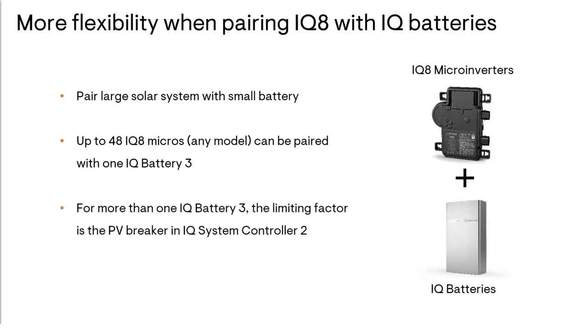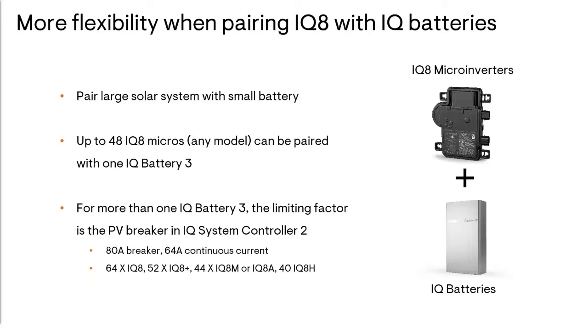Now, if more than one IQ battery 3 is being installed, which is going to be the case most of the time, I imagine, the limiting factor then is the 80 amp breaker in the IQ system controller, which means that up to 64 amps of continuous current can feed from the IQ combiner solar circuits.